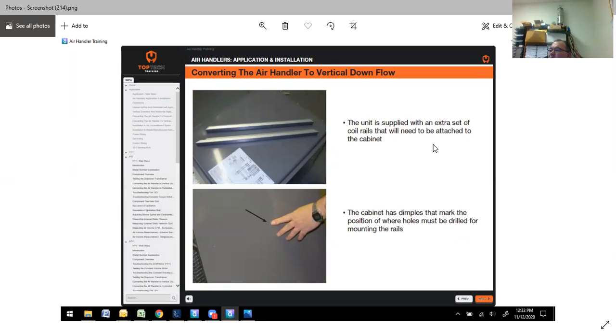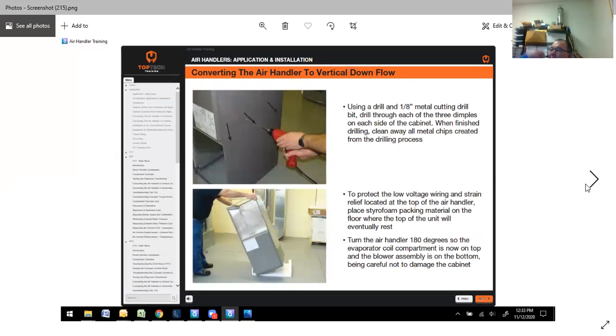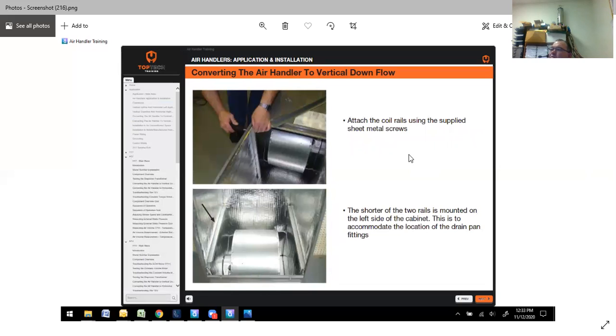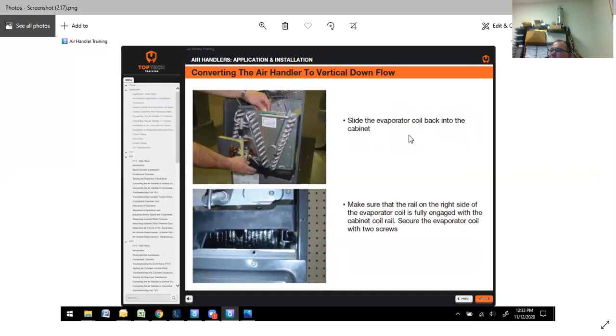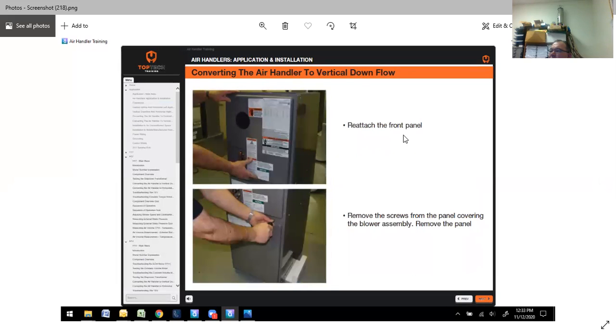The unit is supplied with an extra set of rails. There again, you do see the dimples that you need to screw into or drill into. Once you make those drill holes, to protect the low voltage wiring and strain relief located at the top of the air handler, place styrofoam packing down here at the bottom so it doesn't cause any damage. Turn the air handler 180 degrees so the coil compartment is now on top of the blower compartment. Attach the coil rails using the supplied sheet metal screws. The shorter of the 2 rails is mounted on the left side of the cabinet. This is to accommodate the location of the drain pan fittings. Slide the evaporator coil back into the cabinet. Make sure that the rail on the right side is fully engaged. Reattach the front panel. You're good to go.